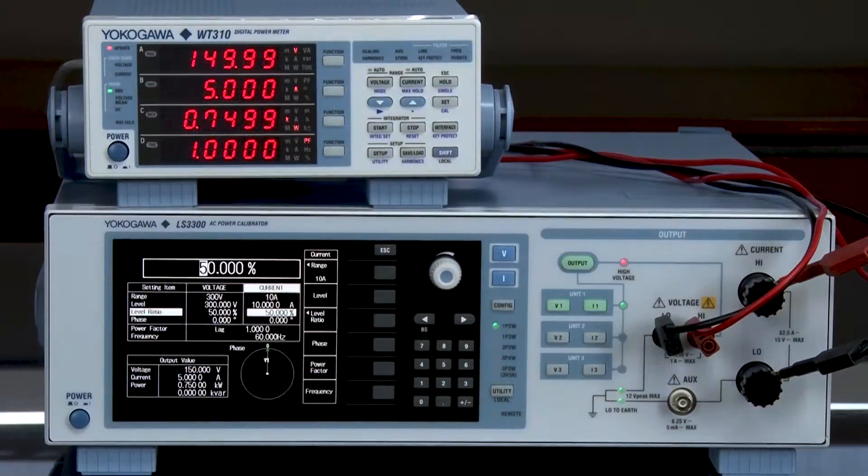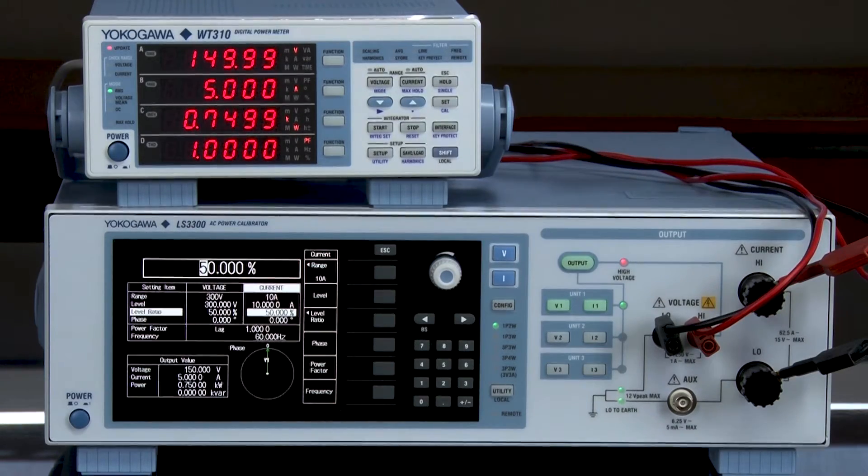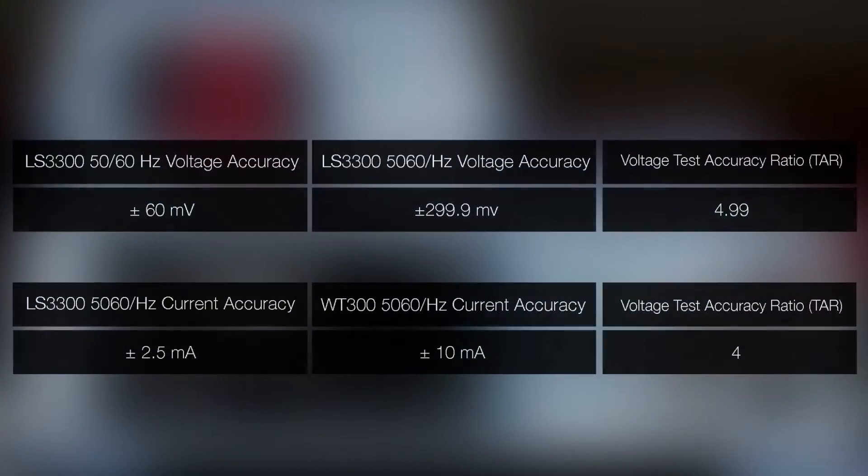The results are seen here on the WT310 power analyzer. From these results the accuracies for both the LS3300 and the WT300 were calculated. For the LS3300 at 60 Hertz, the voltage accuracy at this range and setting is plus minus 60 millivolts with the WT300 accuracy being plus minus 299.9 millivolts. This provides a TAR or test accuracy ratio for voltage equaling 4.99, passing the minimum required ratio.